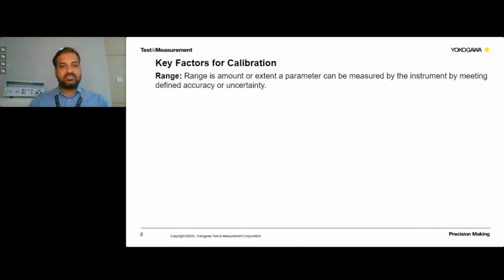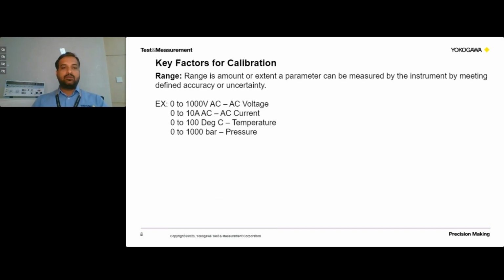So what is range? Range is basically the minimum value and the maximum value that can be measured by any measurement instrument. So that is called range. It is defined by a set of values in terms of the minimum value and the maximum value. In a simpler way, it is the extent of a parameter that can be measured by the instrument, and by doing so, there should not be any compromise on the defined accuracy. While complying with the accuracy, it has to measure the range of values.